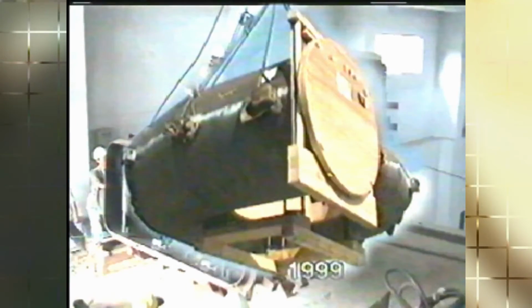The spiral case will be embedded in concrete and therefore shall be provided with stiffeners and anchorages sufficient to ensure that no deformation will take place during concreting. There shall also be provided a sufficient number of leveling screws or jacks, lugs and anchor rods with turnbuckles for supporting and holding the case during placing of concrete. Placed by civil contractor.